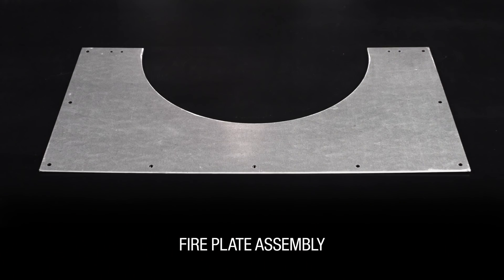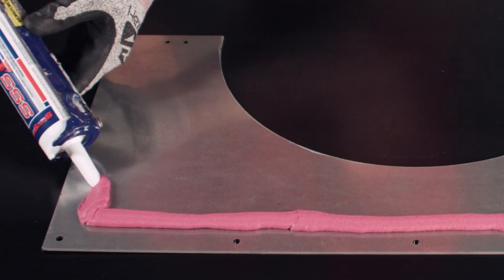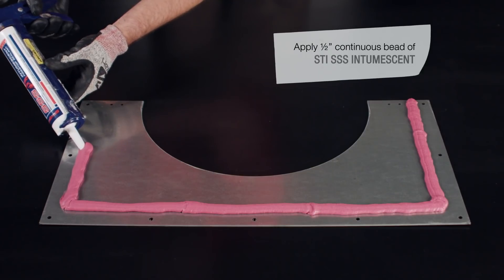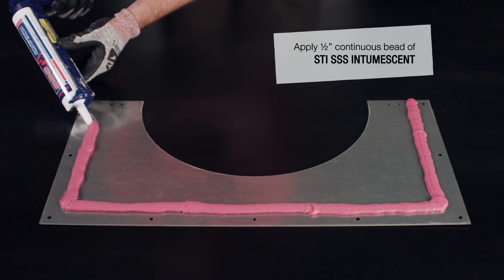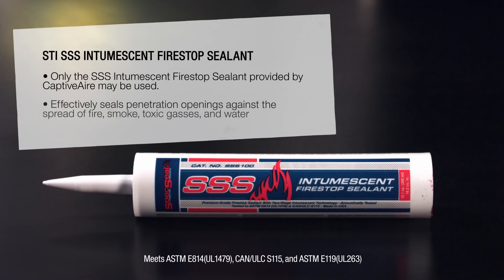You must then install fireplates on the underside of the floor or ceiling. Begin by applying a half inch continuous bead of STI triple S intumescent around the edge of the first fire plate.